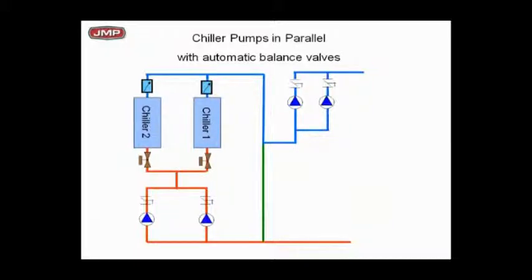But if you've got to pipe them this way, and they're not dedicated pumps in a primary or secondary loop, you need to put two-way isolation valves on each chiller as shown, and load limiters on each chiller just to protect them.